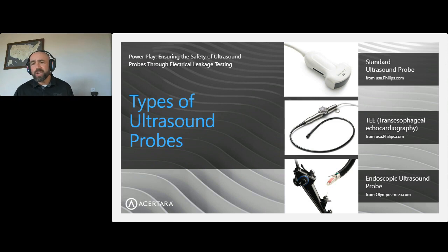That may not always agree with the electric leakage tester that you're using. Some have just standard programmed values, right? It might say if you go over 175 microamps, it fails. If it's under 175 microamps, it doesn't fail. And those electric leakage testers are ubiquitous. They're used quite frequently. I tend to believe that it's better to be able to see the specific value and to be able to set the limits in your tester based on what the OEMs are telling us are the specific limits for that probe, and to be able to understand sort of where that falls in the whole range of available values.